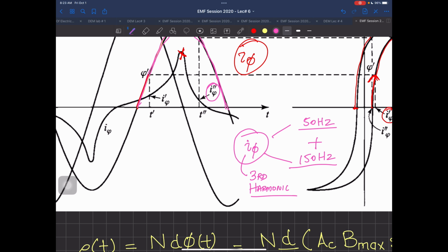Harmonic means a multiple of the fundamental frequency. What is 50 hertz? That's the fundamental frequency, and in Pakistan the fundamental frequency is 50 hertz. So your core, because of saturation, is taking on a third harmonic, which is 3 times 50, or 150 hertz.